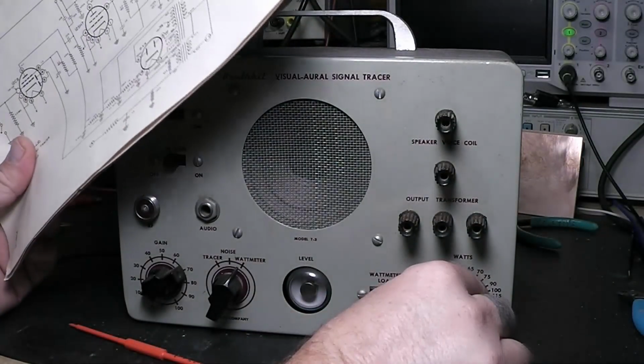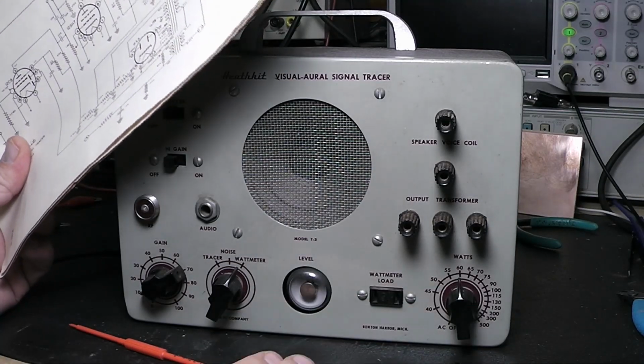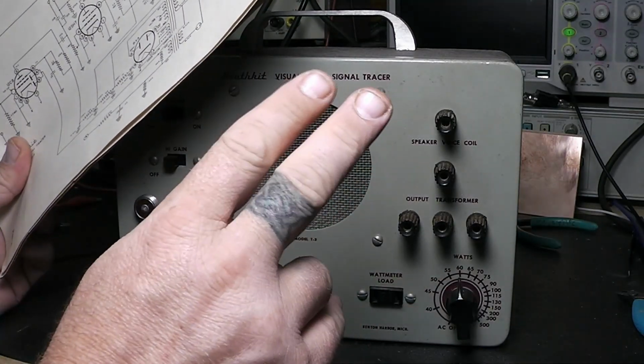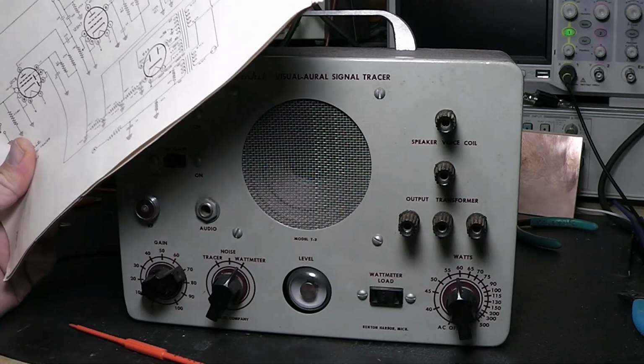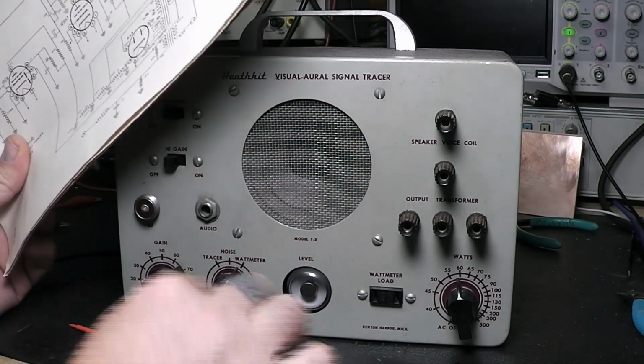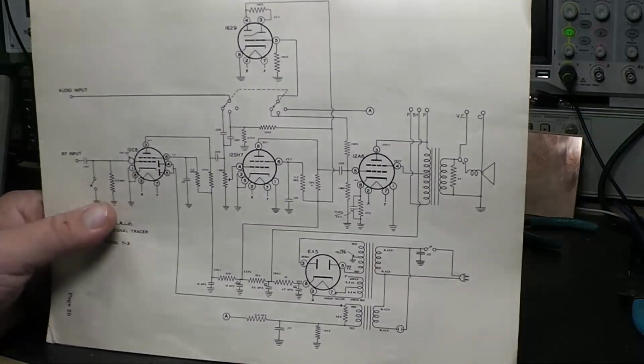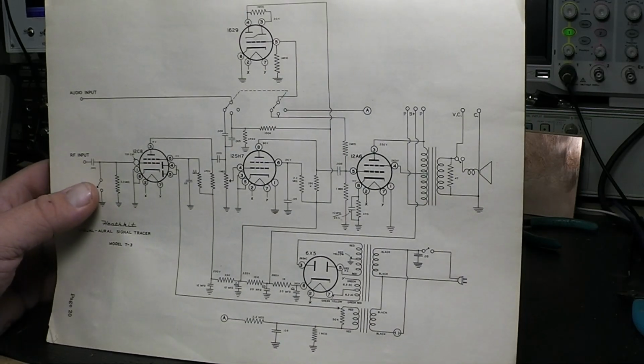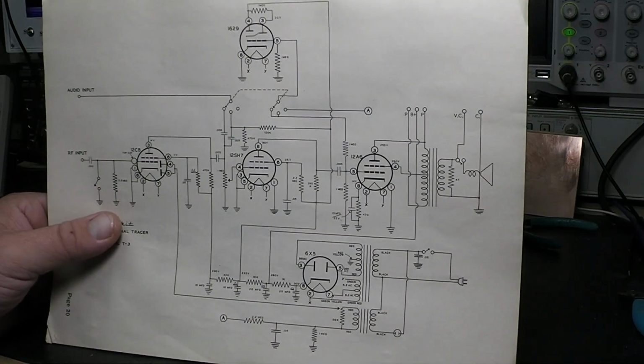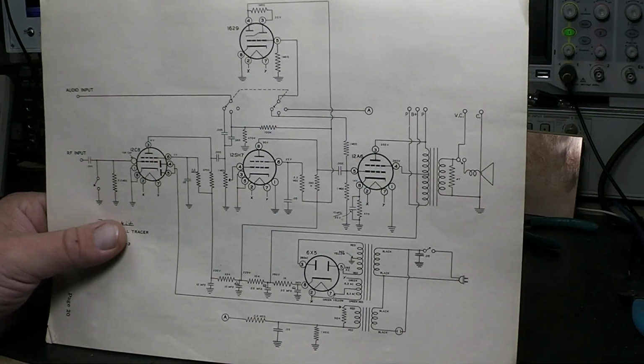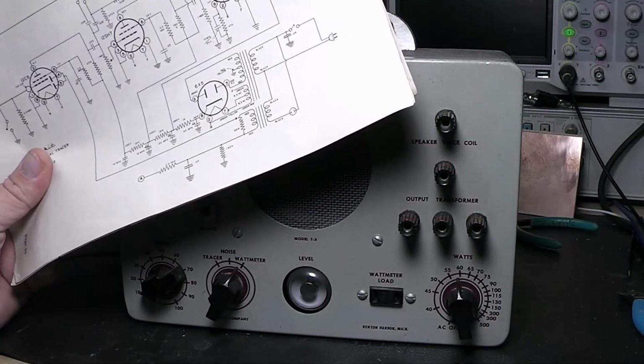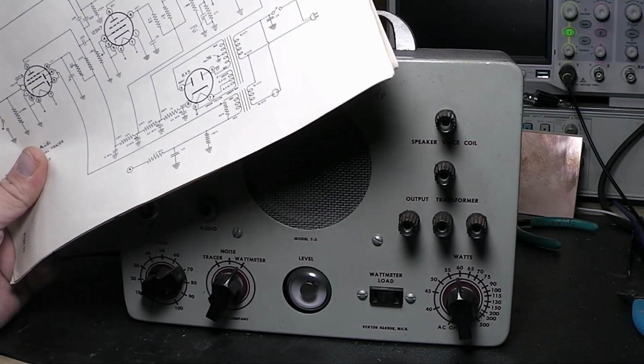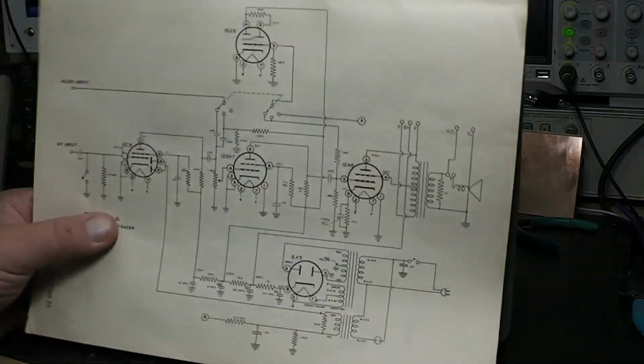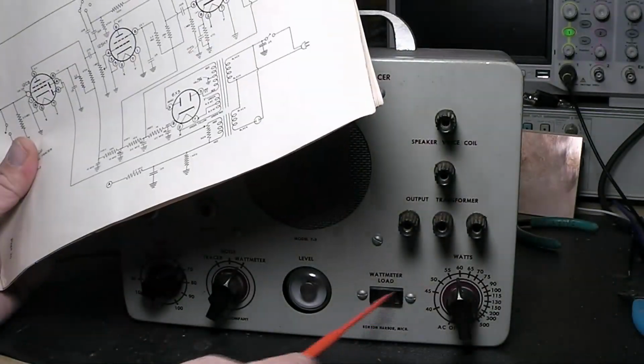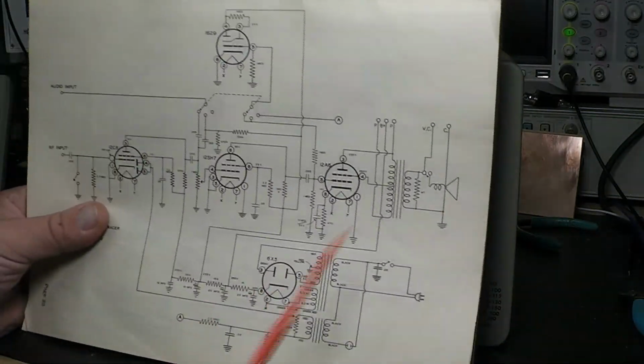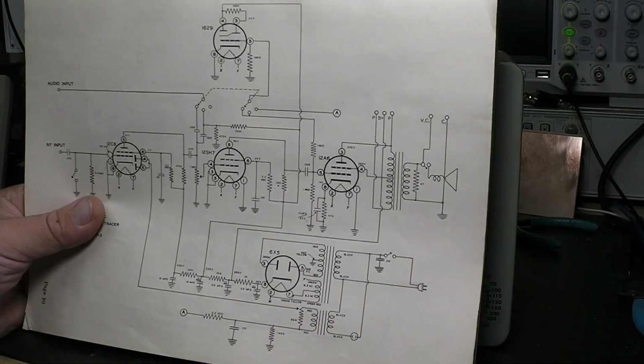So somewhere around in here, you should see that eye tube start to open. And when it just starts to open, that's where you read your wattage at. A good thing is if you got a 65 watt bulb, a 60 watt bulb, or a 75 watt incandescent bulb - not any of these newer LEDs or anything like that - they're good to use to calibrate this and make sure it's right. If not, you have to check the circuit out and see what's going on.